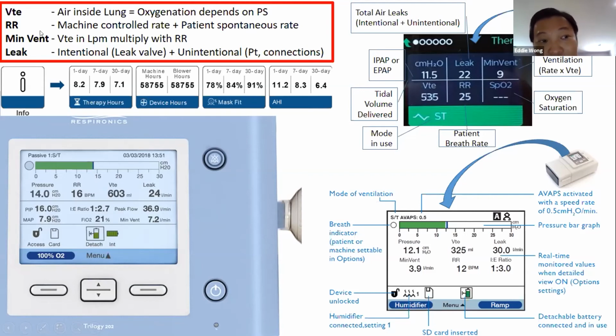So whenever you see low minute ventilation, the first thing in your mind is: is it my volume problem or my rate problem? If my rate is normal, what is causing the volume to drop? Is it the leakage, or the circuit disconnection, or is my alarm set too sensitive? Is it too sensitive to set as a low minute ventilation alarm? Normally I will set 1 liter per minute, because sometimes with too many alarms the patient will be worried, and the family will be worried at home.